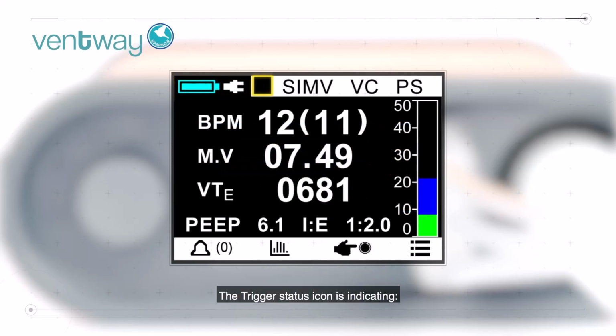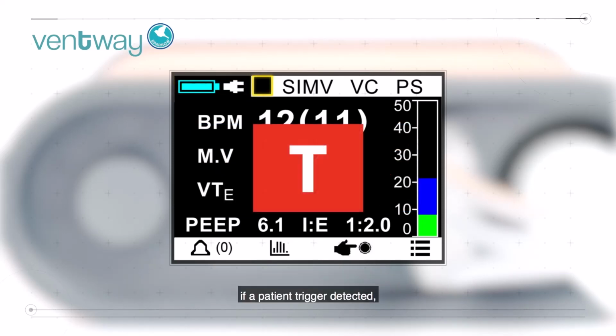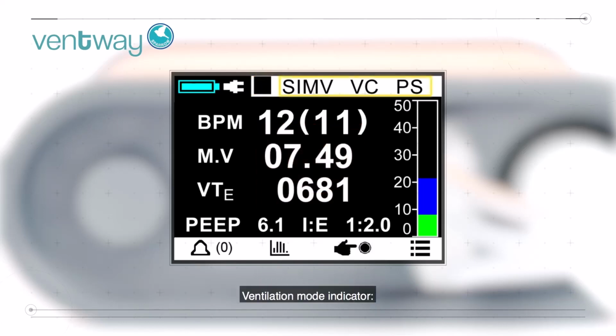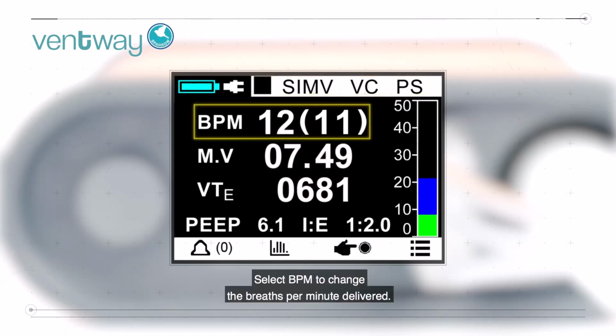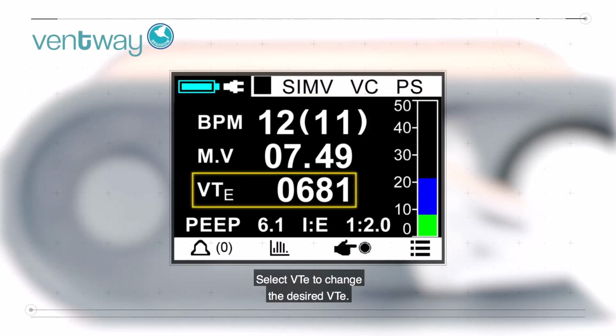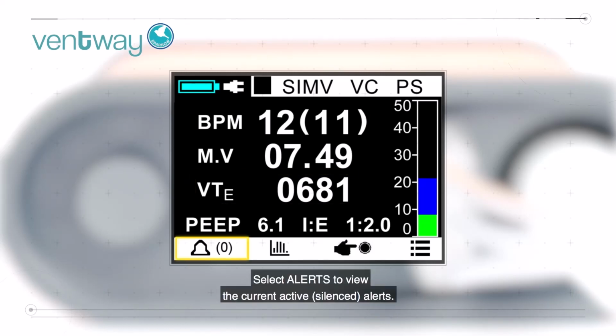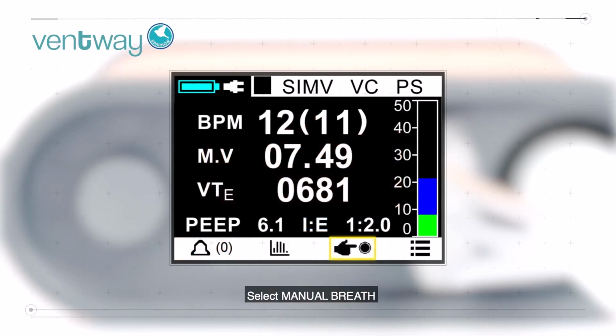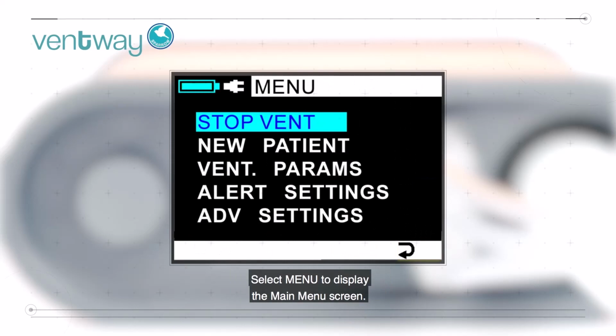The trigger status icon indicates if a patient trigger was detected, if pressure sensors are currently being zeroed, or if a cough was detected. Ventilation mode indicator. Select BPM to change the breaths per minute delivered. Select VTE to change the desired VTE. Select Alerts to view the current active and silenced alerts. Select Manual Breath to give one breath to the patient using the current parameters. Select Menu to display the main menu screen.